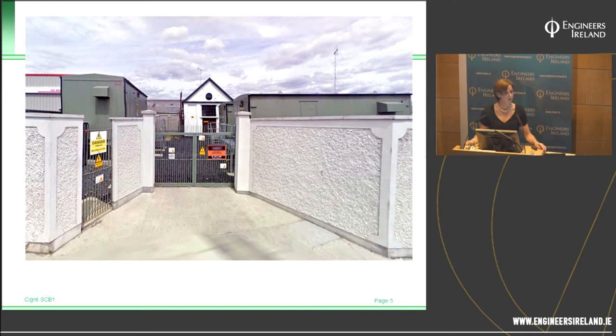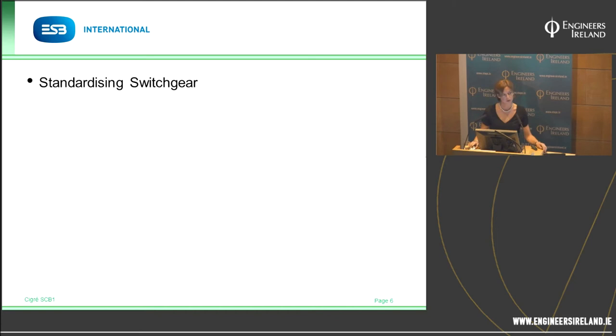Now, in some cases, there were MV lines crossing the station, and we couldn't get an outage on those lines. And in those cases, we used the jack and skid method to install the modules, whereby we slid the modules into position. Other efficiencies were gained through standardising switchgear, control and protection.